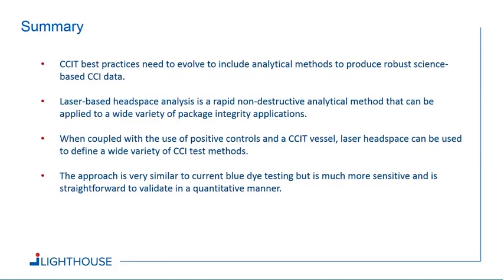And when you talk about using this technique with a CCIT vessel, I think this approach is very similar to current blue dye testing, but you can imagine it's much more sensitive. You're using an analytical method to detect small amounts of gas ingressing into the container. And what's nice about it is it's relatively straightforward to validate in a quantitative manner.